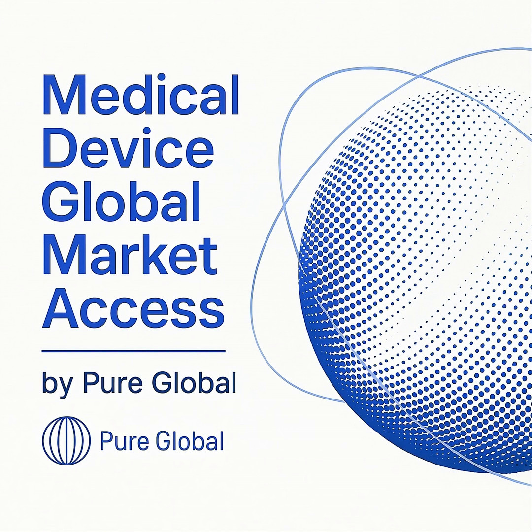The NMPA provides a few pathways. First, check if your device is listed in the NMPA's Catalog of Medical Devices exempt from clinical evaluation. If it is, the process is significantly streamlined. If not, you may be able to leverage clinical data from an equivalent device already approved in China. It is also possible to use your overseas clinical data from the EU, but this often requires supplementary data or justification to demonstrate compliance with Chinese clinical requirements. If these pathways are not viable, a local clinical trial in China becomes necessary.